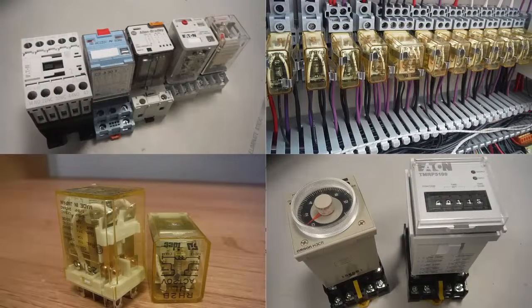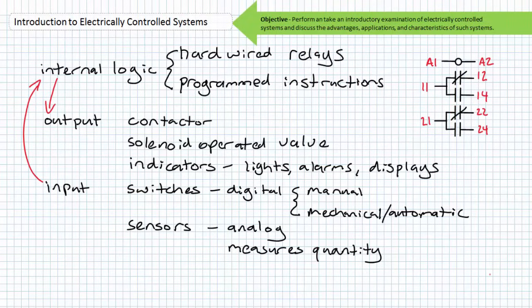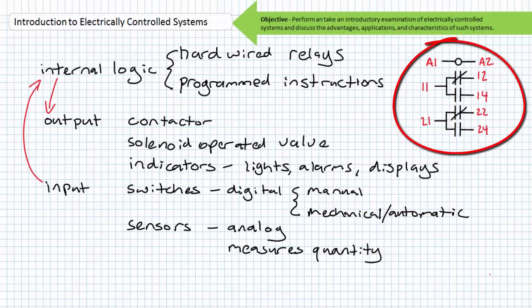A control relay can take many forms. General-purpose control relays have a collection of normally open and normally closed switches that change states when the coil of the relay is energized. Timer relays perform timing functions, and counter relays can count. The control relays mimicked by a PLC instruction set perform additional high-level tasks. Whether the control relay is a physical device or a mimicked instruction set, it can be thought of as a device with a coil and a set of associated contacts that change states when the coil is energized. Both the coil and the contacts of a control relay switch only control level signals.